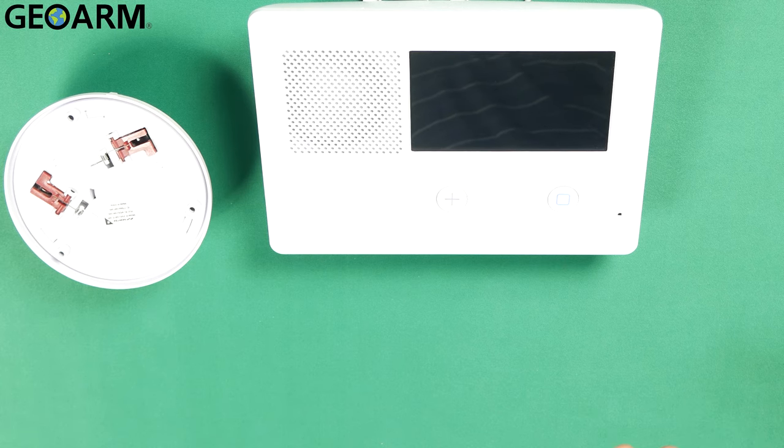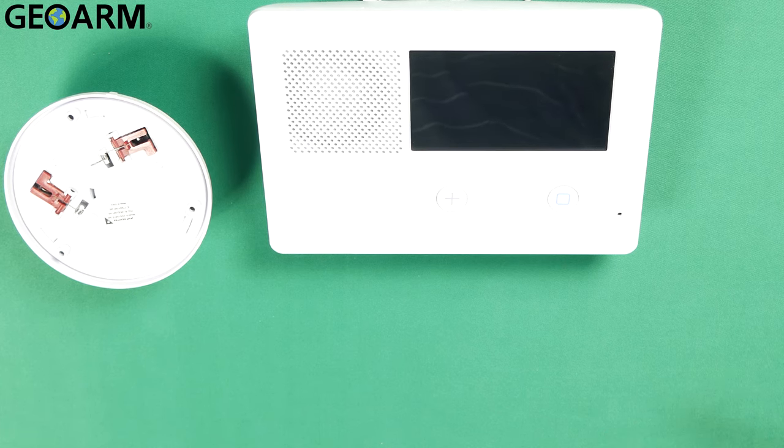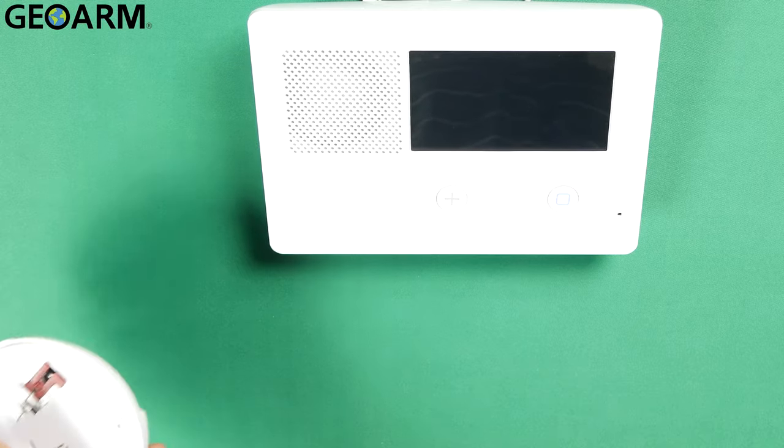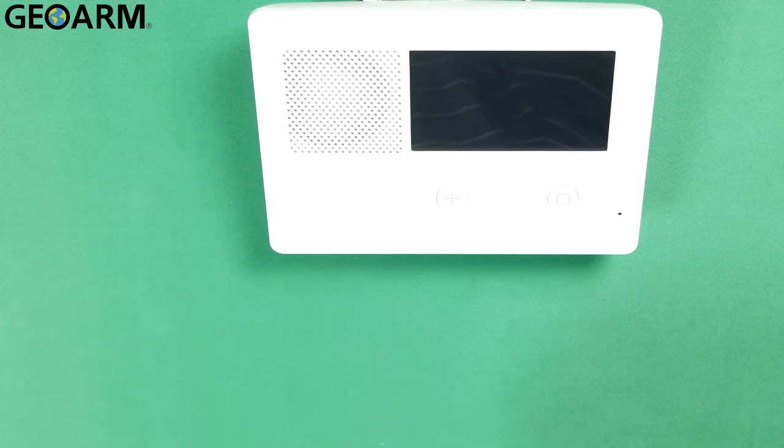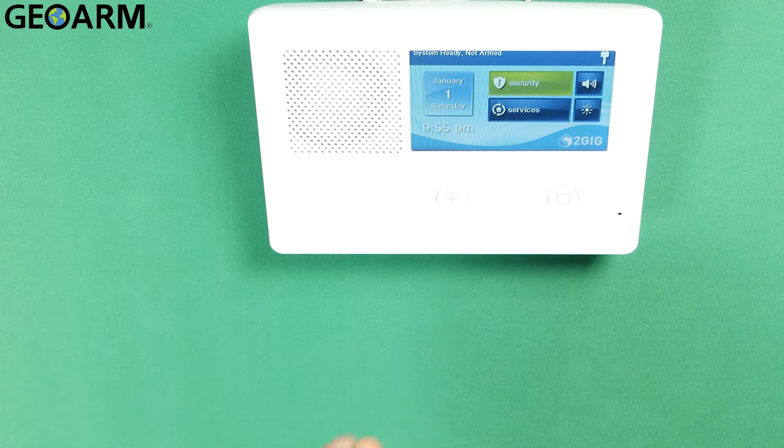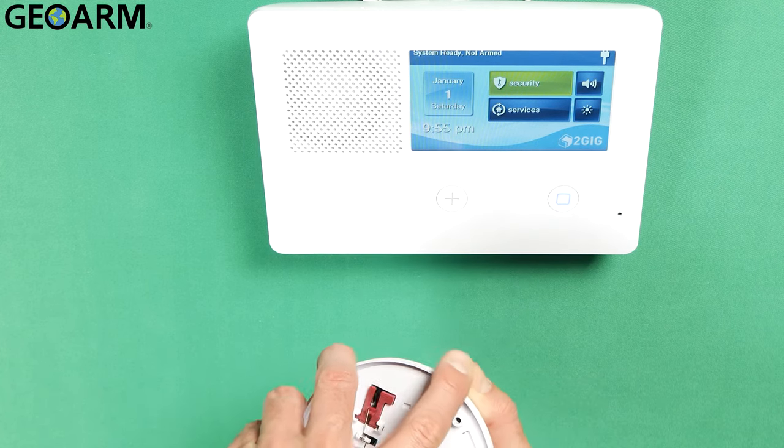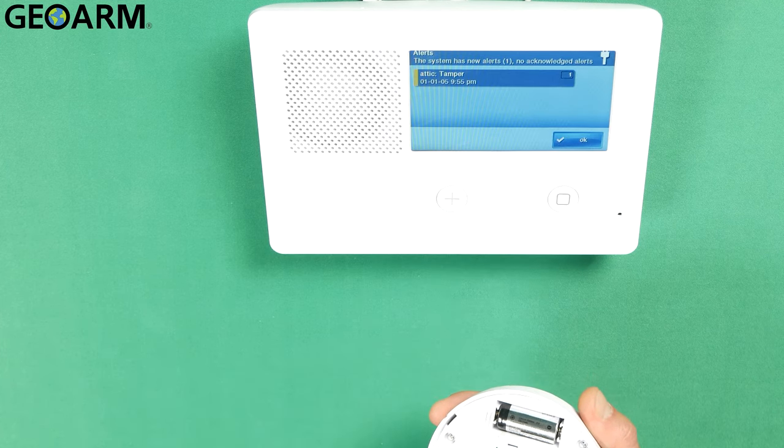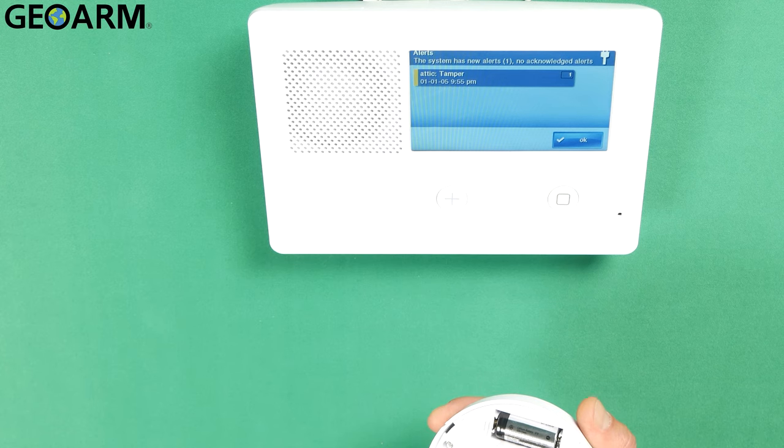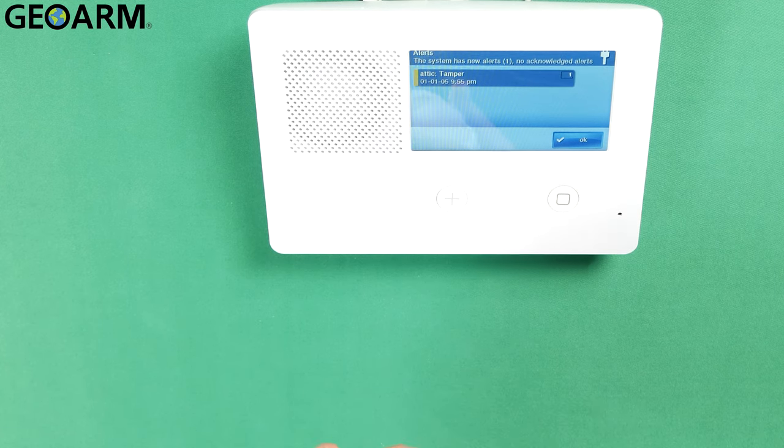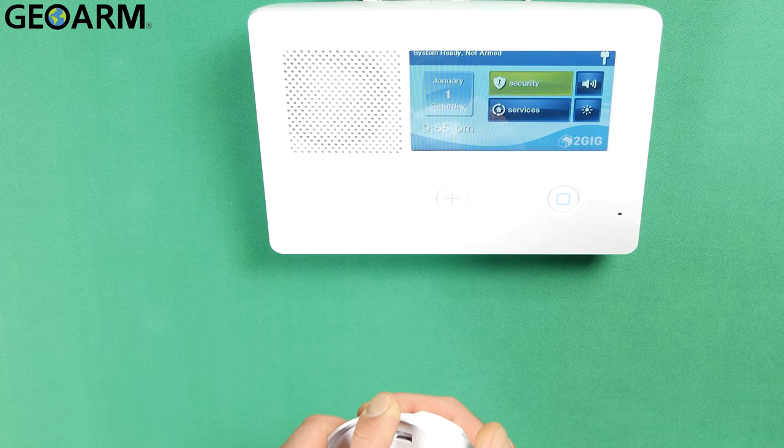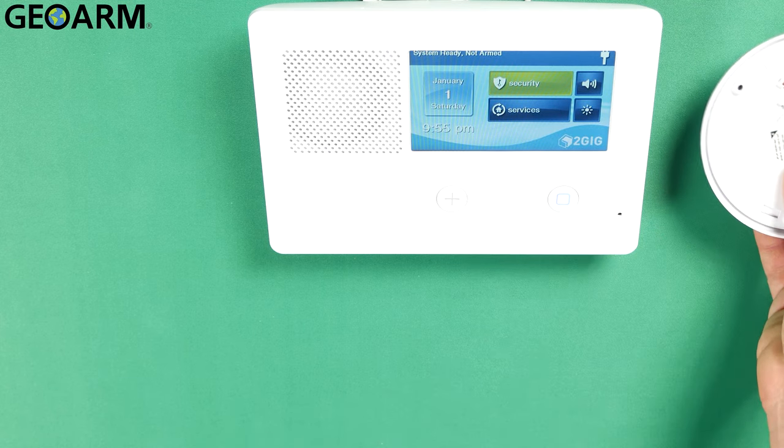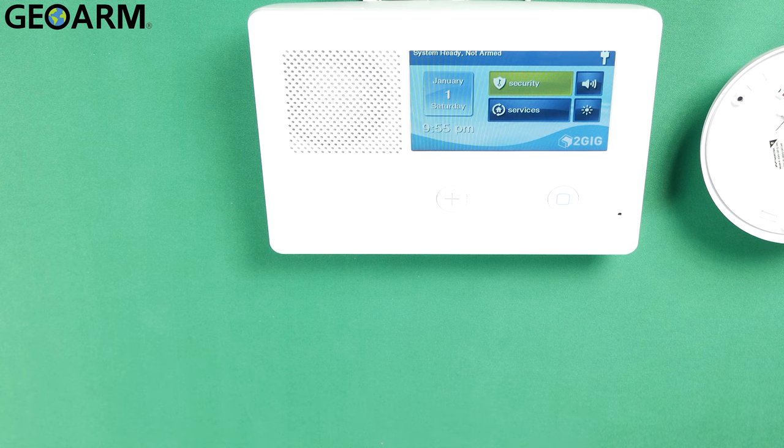And once the device comes back up and we get our touch screen I should be able to tamper this and it should tell us on the panel that it's actually learned in. So we'll check it out here. System ready not armed. Let's tamper it. And then we'll put the cover back on to make sure that this thing is programmed in correctly. So system ready not armed. So we're good to go.